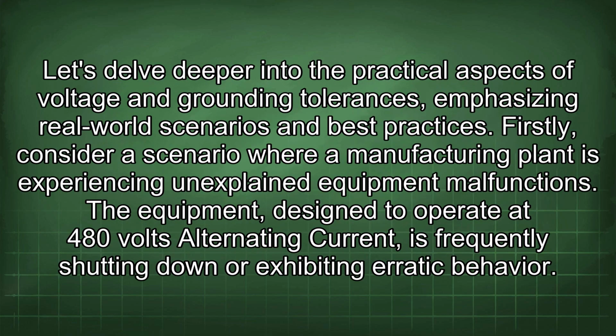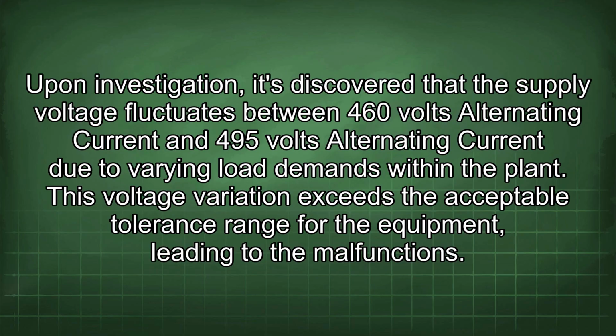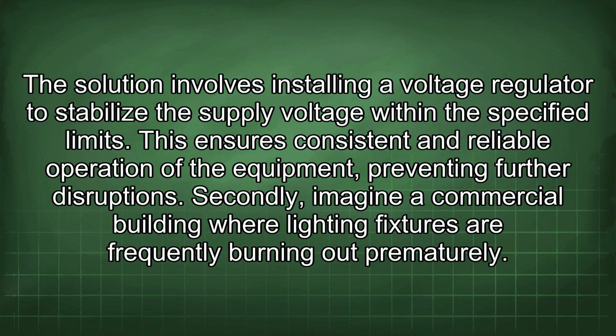Let's delve deeper into the practical aspects of voltage and grounding tolerances, emphasizing real-world scenarios and best practices. Firstly, consider a scenario where a manufacturing plant is experiencing unexplained equipment malfunctions. The equipment, designed to operate at 480 volts alternating current, is frequently shutting down or exhibiting erratic behavior. Upon investigation, it's discovered that the supply voltage fluctuates between 460 volts alternating current and 495 volts alternating current due to varying load demands within the plant. This voltage variation exceeds the acceptable tolerance range for the equipment, leading to the malfunctions. The solution involves installing a voltage regulator to stabilize the supply voltage within the specified limits. This ensures consistent and reliable operation of the equipment, preventing further disruptions.